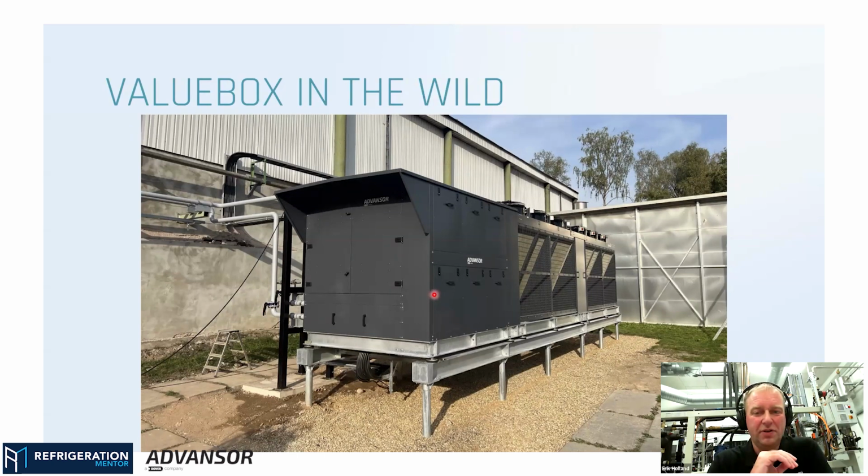And you don't want to do this too fast, because a water circuit is a really slow system, and the control system here is set to be really, really slow in order to catch those small fluctuations in temperature. So just because you raise your return water temperature, your incoming water line, by a Kelvin or something, it's not going to cut in all the compressors and go to full load, because that would create a lot of instability. So we have to go really slowly here. It's best done in hand mode. Just set the system in hand mode and slowly work it up and check that everything is okay.